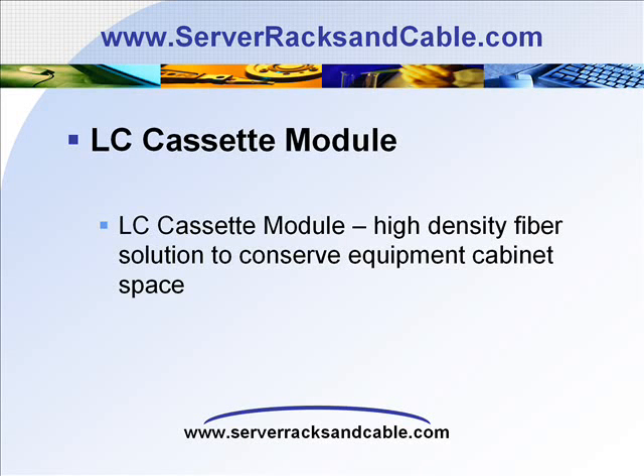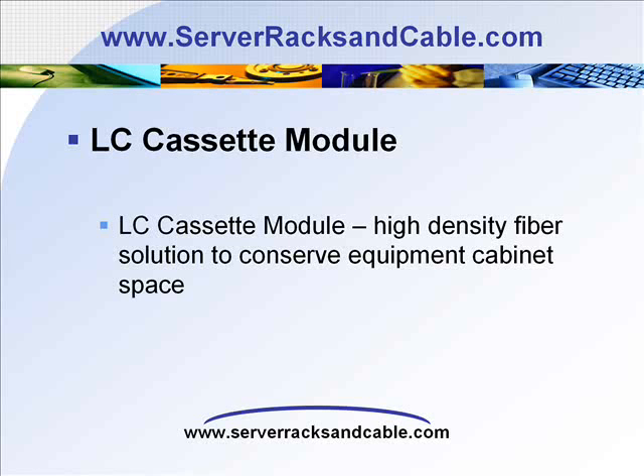The fiber is pretested, pre-terminated, and essentially plug and play. The error that can be introduced by pulling individual strands across multiple floors plus polishing and termination doesn't happen. To expand to new servers, a trunk cable with MTP connectivity can be dropped in and be up and running very quickly. All the cabling and cassettes do not have to be installed up front with necessary capital expenditure — the network can be deployed as the servers and switches are increased.